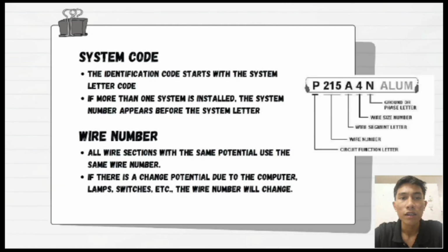System code: the identification code starts with the system letter code. If more than one system is installed, the system number appears before the system letter. Wire number: all wire sections with the same potential use the same wire number. If there is a change in potential due to a computer, lamps or switches, the wire number will be changed.